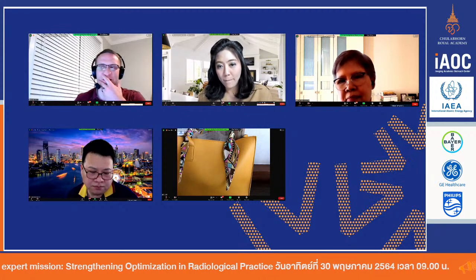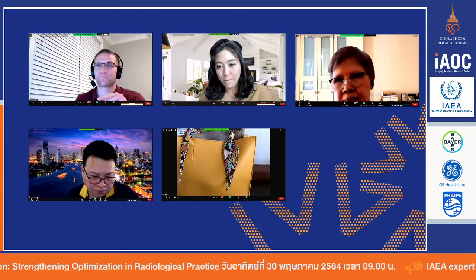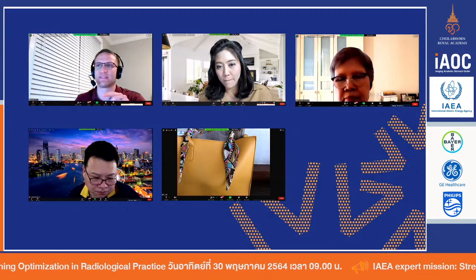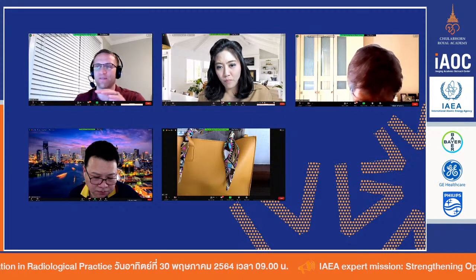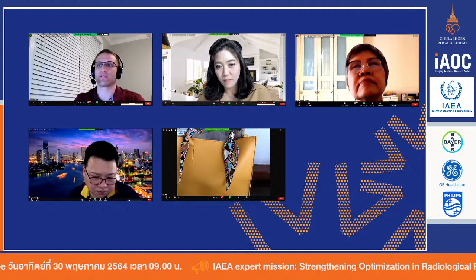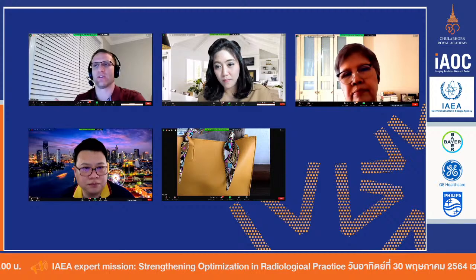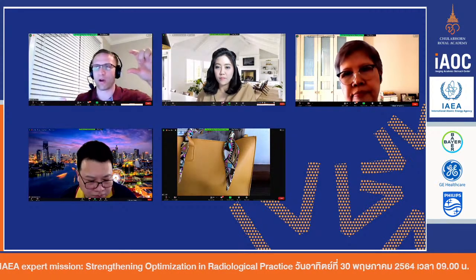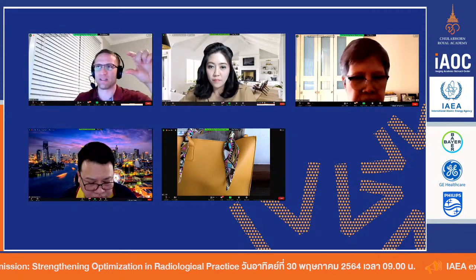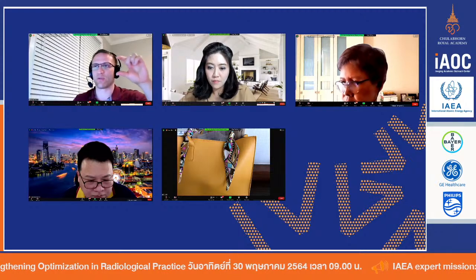The other thing is, as I mentioned, in the future the IEC has defined a way to calculate SSDE for all CT scanners, all vendors. So in the future, the scanner itself will calculate it, and the dose monitoring software will simply receive that number. The software will not need to calculate that number in the future.